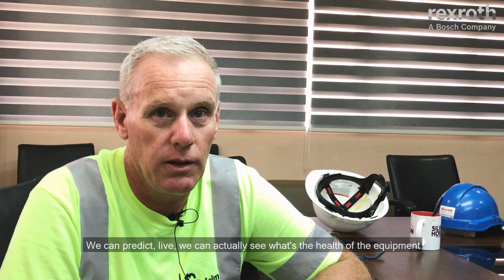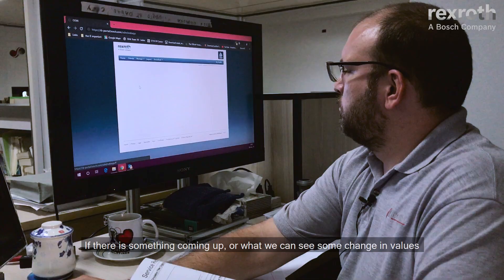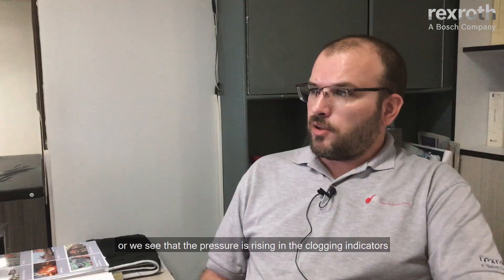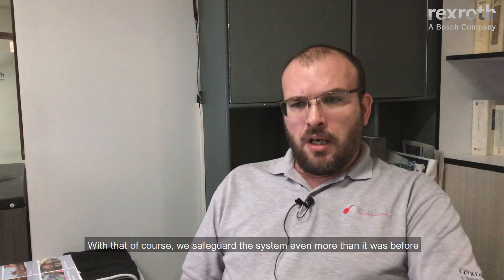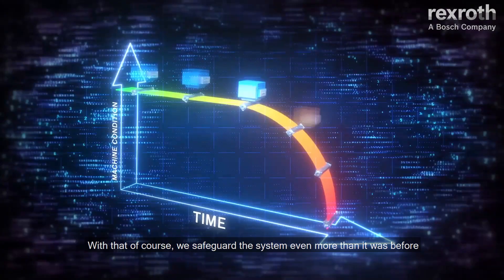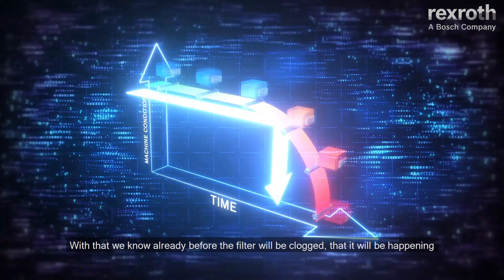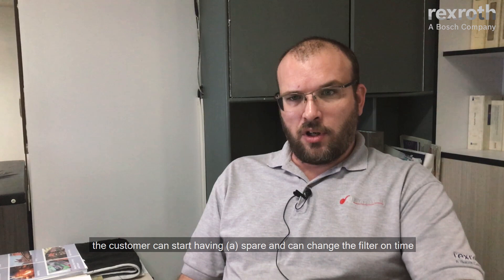We can predict, live. We can actually see the health of the equipment. If something is coming, we can see changes in values, or we see that the pressure is rising in the clogging indicators. We inform the customer that the filter has to be changed. With that, we safeguard the system even more than before — we know before the filter will be clogged that it will happen. The customer can start having spare parts and change the filter on time, so the system is safeguarded.